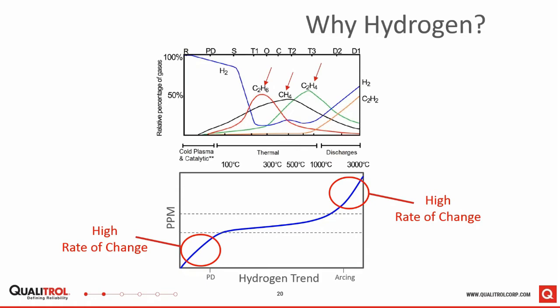Okay, so as Donald's prior slide showed, at lower temperatures, hydrogen starts getting produced, and as the temperature increases, hydrogen is created in the oil at a faster and faster rate. The diagram at the top of the slide shows a percentage basis based on temperature, with temperature on the x-axis and percent on the y-axis. On a percentage basis, at very low temperatures, say in the partial discharge or PD region, you produce almost 100% hydrogen. And typically PD is characterized in DGA by a lot of hydrogen followed by methane.